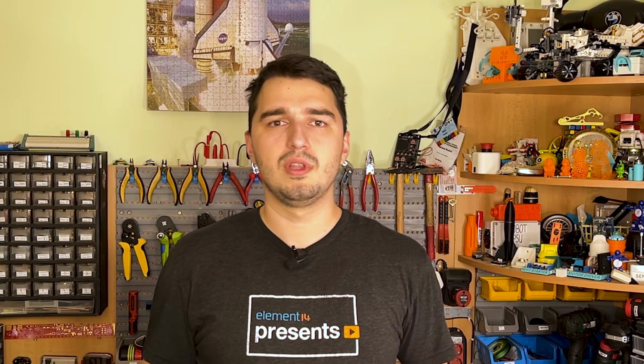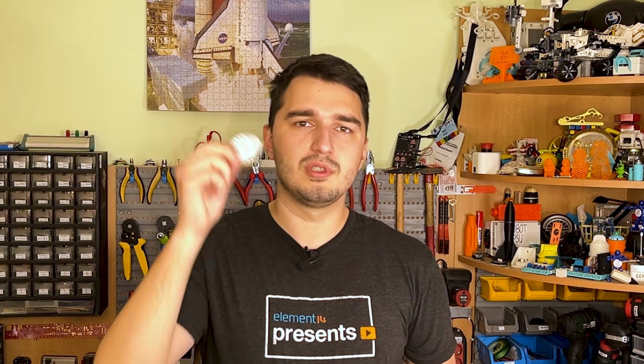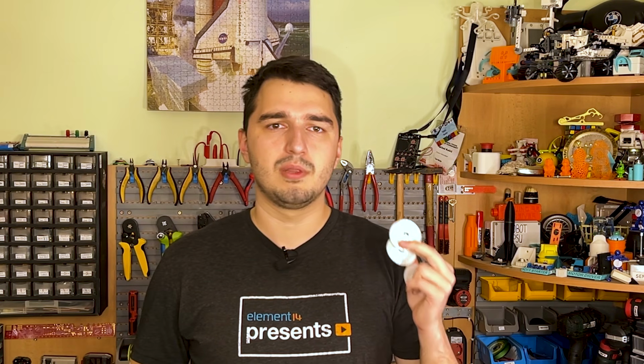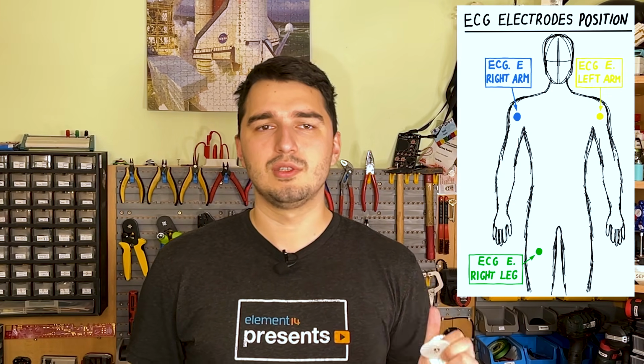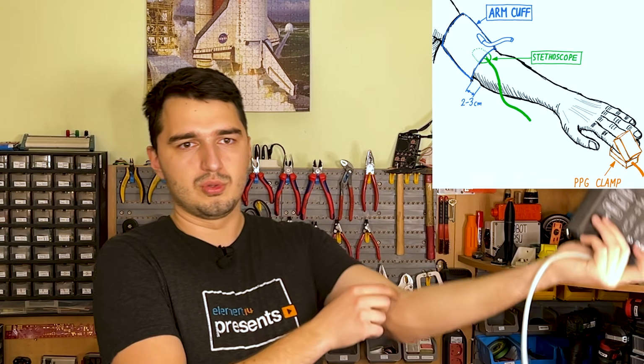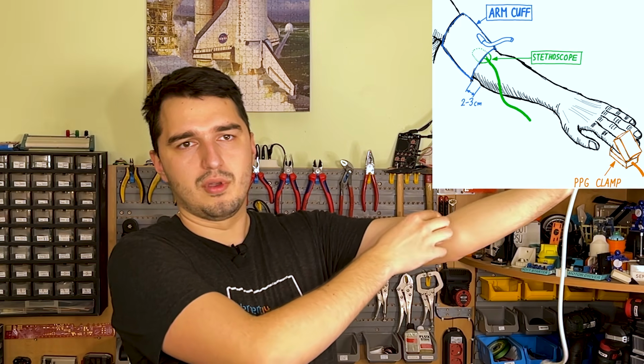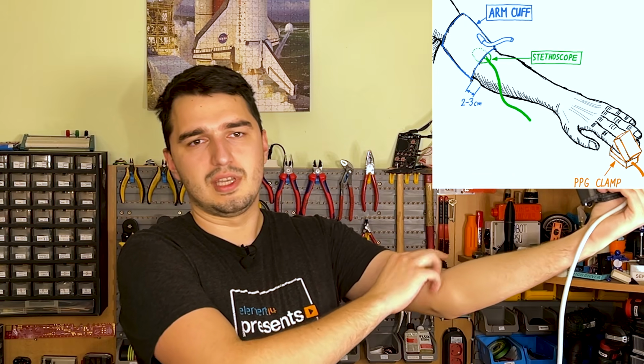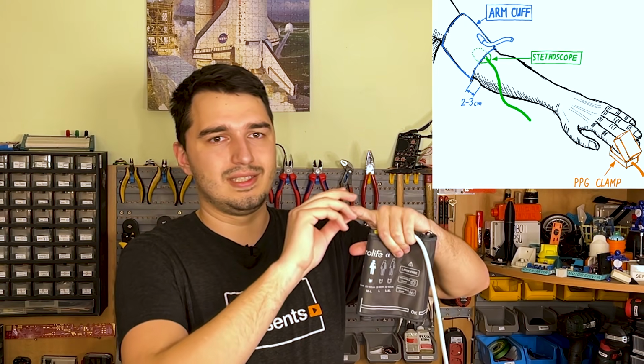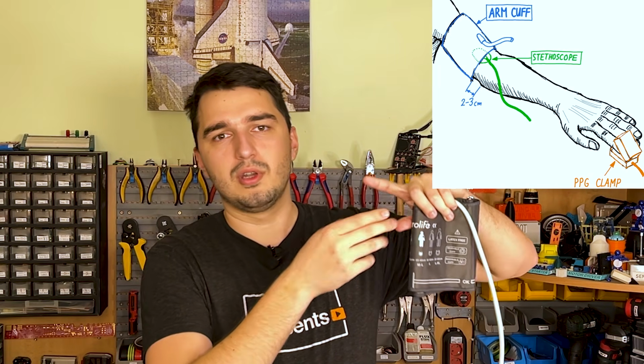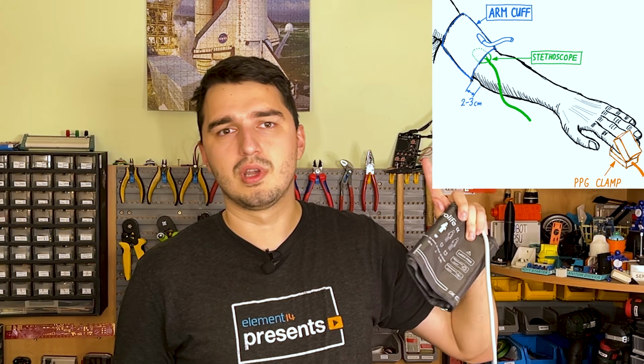After that, we actually conduct measurements with our developed device. First of all, we need to place the electrodes for the ECG, and for that I will be using these sticky electrodes that you can see here. So the placement that we will go for is left arm and right leg, as you can see in the drawing here. Now, the other thing that we need to do is place all of the other equipment on the arm. That includes the arm cuff, which should go about 2 to 3 centimeters above your joint here. Then underneath that goes the stethoscope, right somewhere around here. And on the same arm, on your index finger, you want to put the PPG clamp, and you shouldn't press too hard on it. After that is done, you can run the test, as I will show you now, and when you've collected all of the data, we can get to the data analysis.